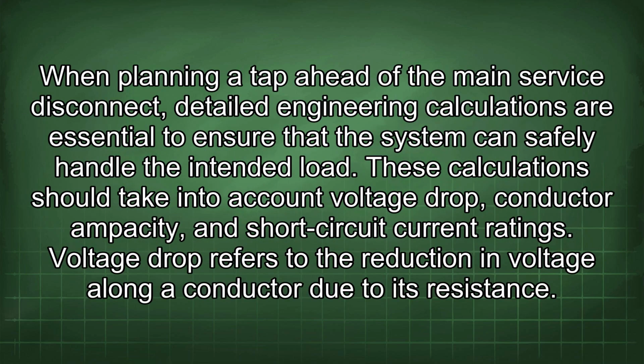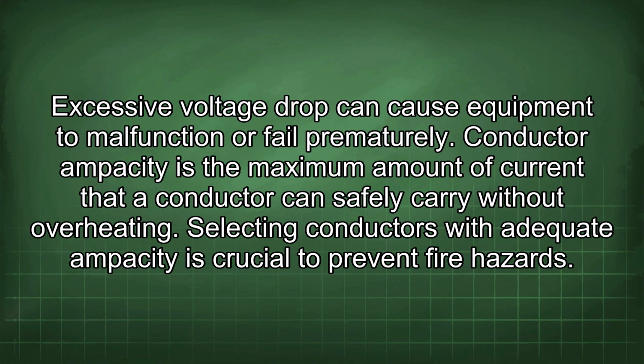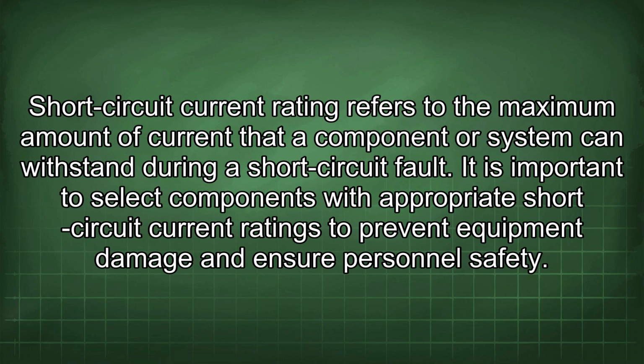When planning a tap ahead of the main service disconnect, detailed engineering calculations are essential to ensure that the system can safely handle the intended load. These calculations should take into account voltage drop, conductor ampacity, and short-circuit current ratings. Voltage drop refers to the reduction in voltage along a conductor due to its resistance. Excessive voltage drop can cause equipment to malfunction or fail prematurely. Conductor ampacity is the maximum amount of current that a conductor can safely carry without overheating. Selecting conductors with adequate ampacity is crucial to prevent fire hazards. Short-circuit current rating refers to the maximum amount of current that a component or system can withstand during a short-circuit fault. It is important to select components with appropriate short-circuit current ratings to prevent equipment damage and ensure personnel safety.